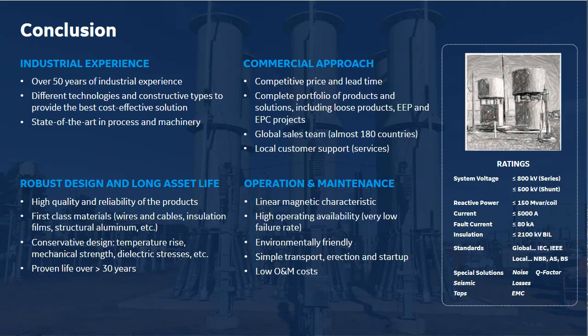So can you tell us more about the low loss design? Thank you for this question. Very good question indeed. So I mentioned the four different types of conductor materials that we have: a squared shape, rectangle shaped profile, or single wire, or stranded cable, or flat transposed cables. For each one of these conductive materials or technologies, there is a particular characteristic and a particular application in terms of sizes. So for small reactors, we can design them with all of these four technologies.